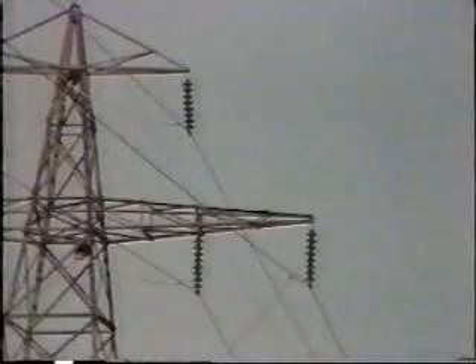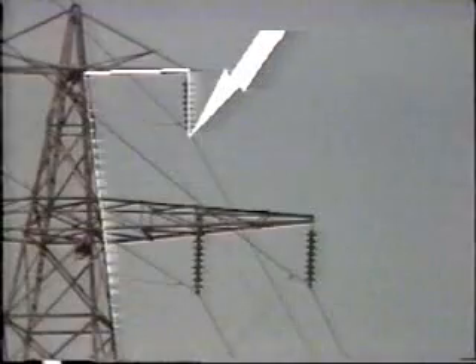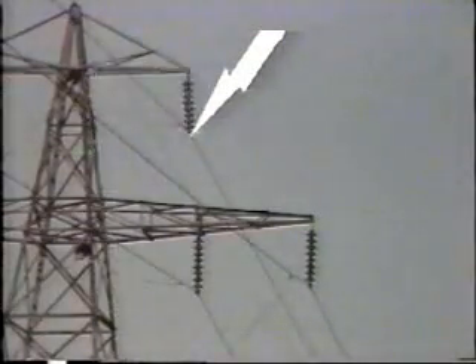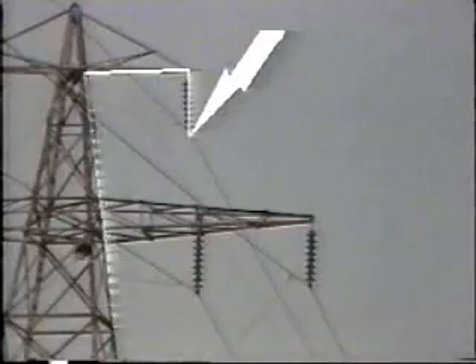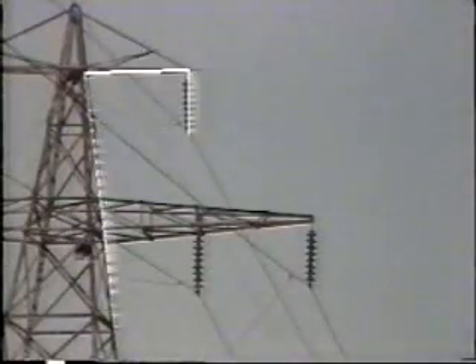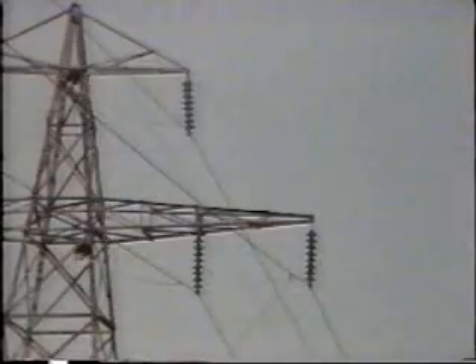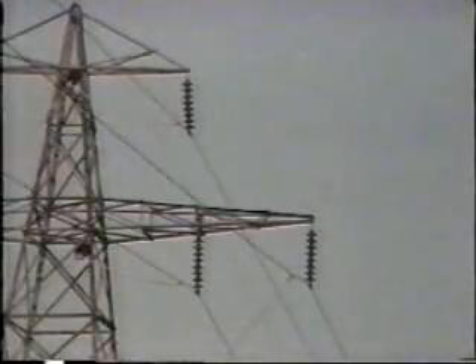ground. The vast majority of circuits are in the form of overhead lines, and in this case the most common fault is a flashover caused by lightning. The extremely high peak voltage of the lightning stroke causes a flashover of the line insulator to ground, and once this is started, the fault current will continue to flow even after the lightning stroke is passed. This phase to ground fault will remain as long as power is being supplied to the line. If two conductors are affected by the lightning stroke, then we would have a phase to phase fault.